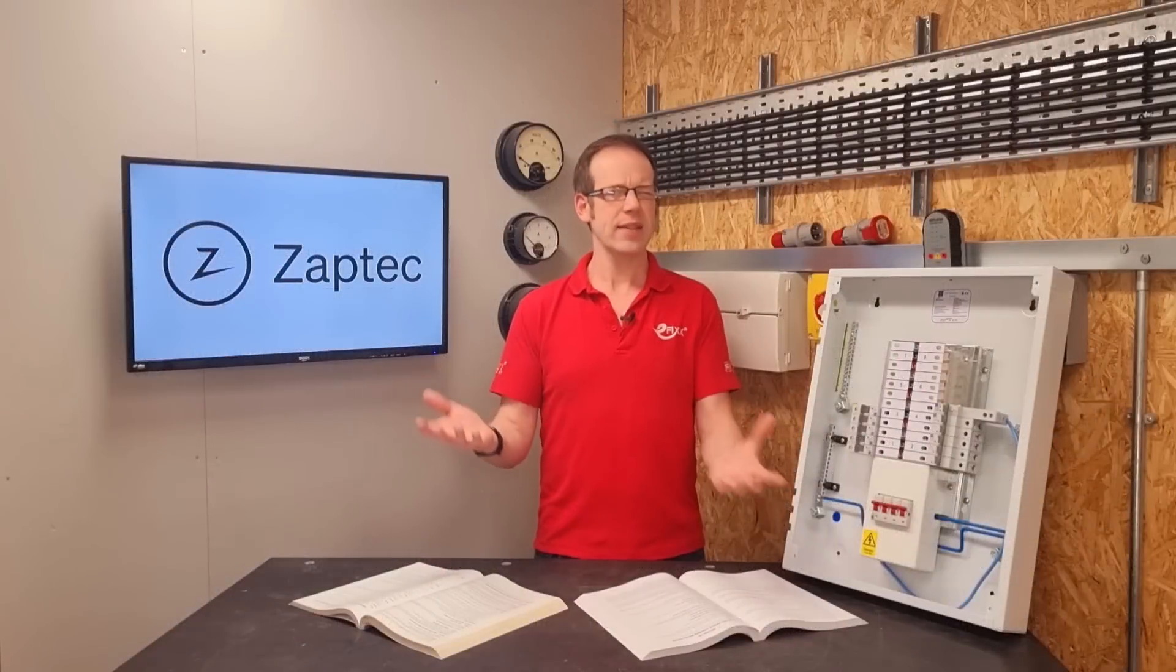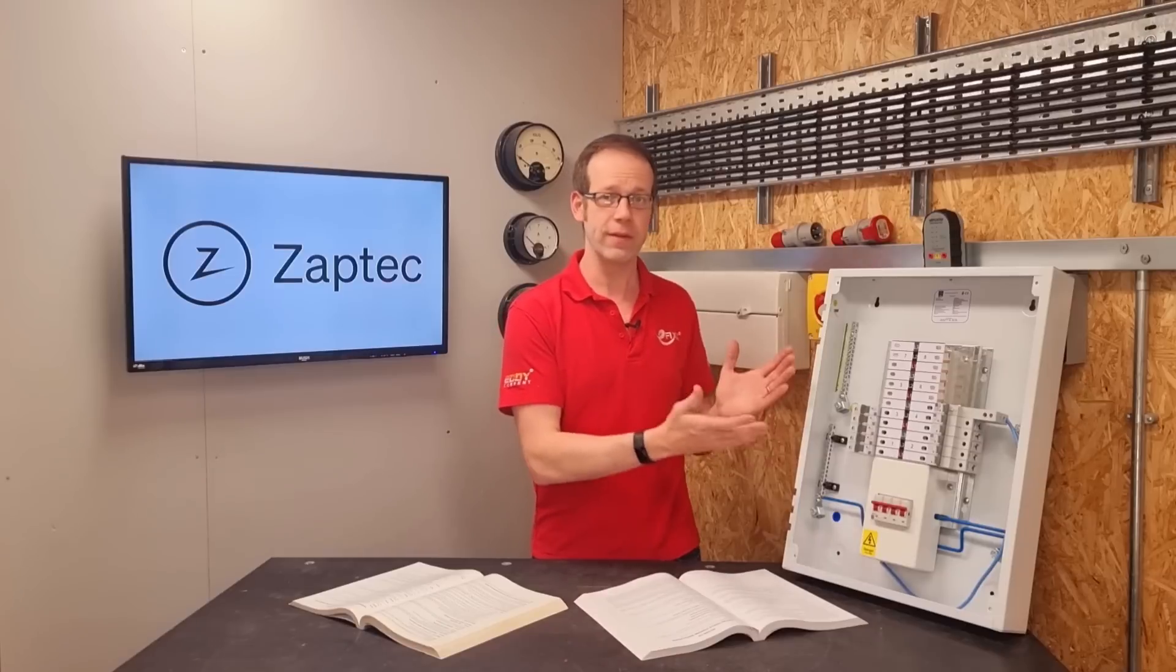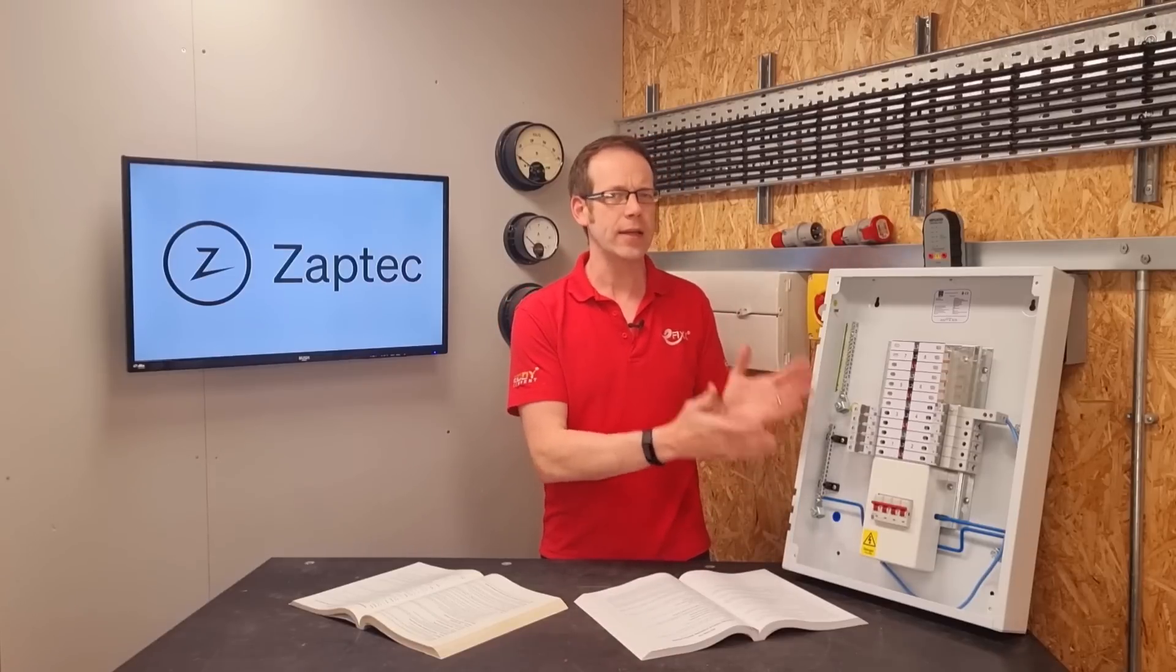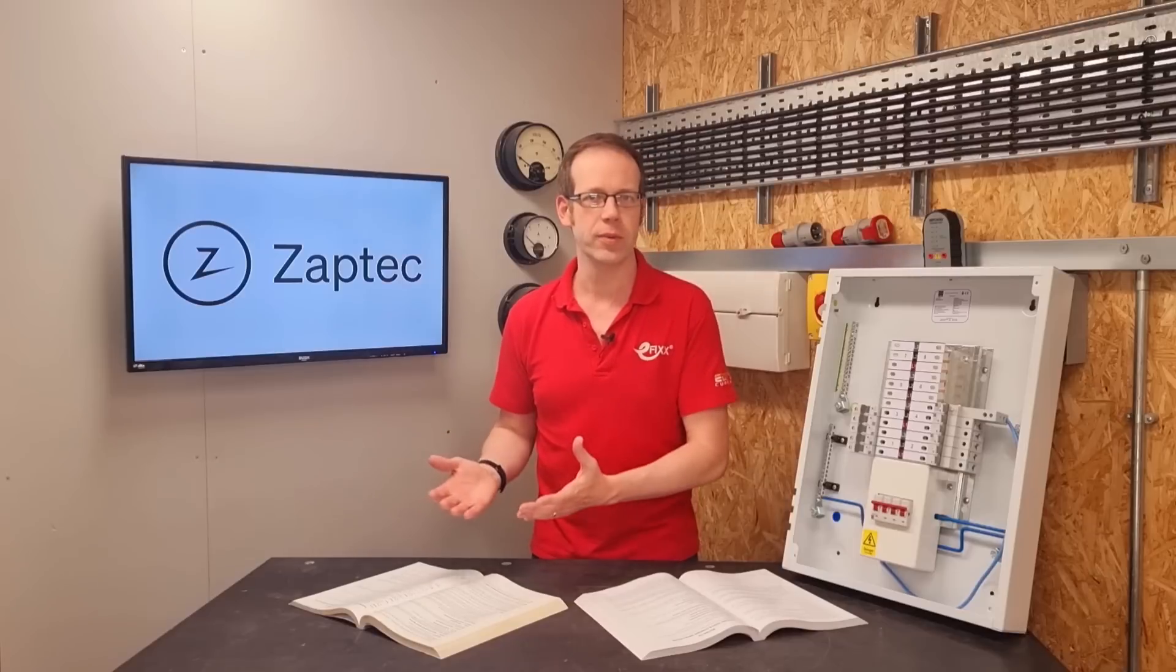So at first glance that seems pretty acceptable—that if we're connecting an EV charge point to an installation fed by a three-phase supply, we can connect the protective conductor to the PME and all will be well. So why was that acceptable?